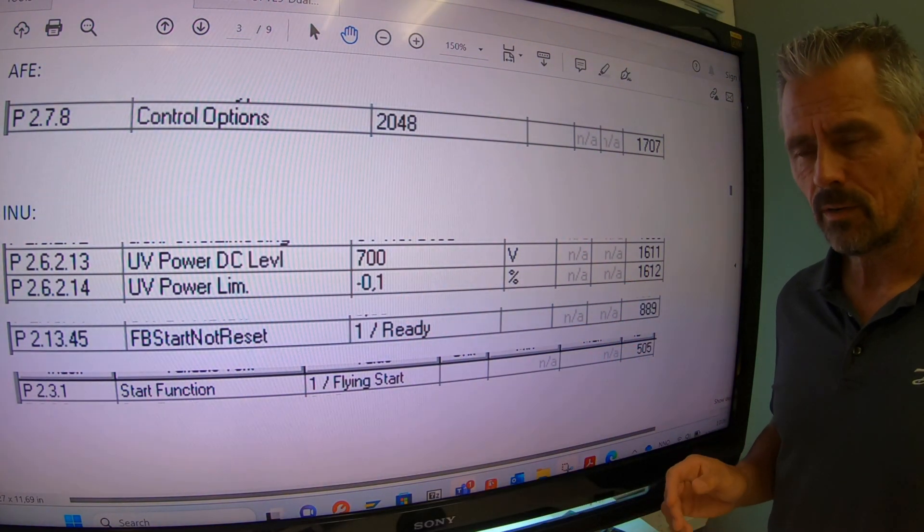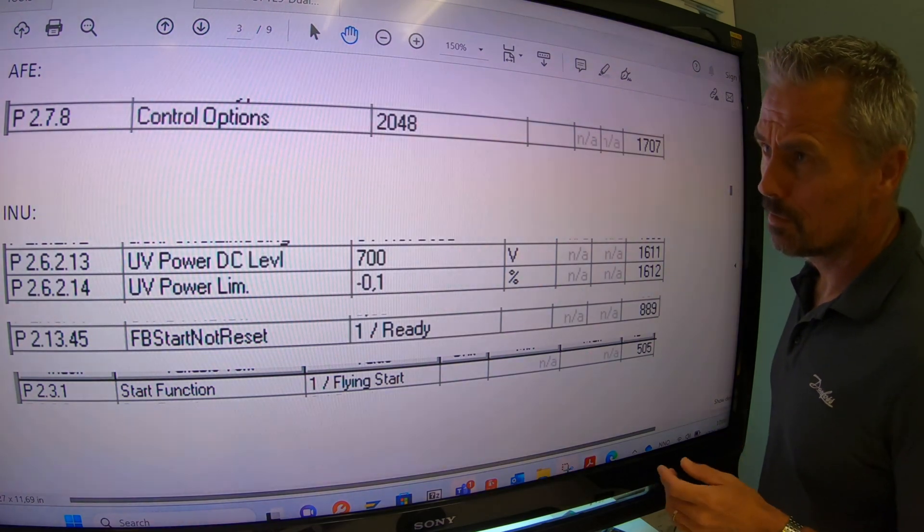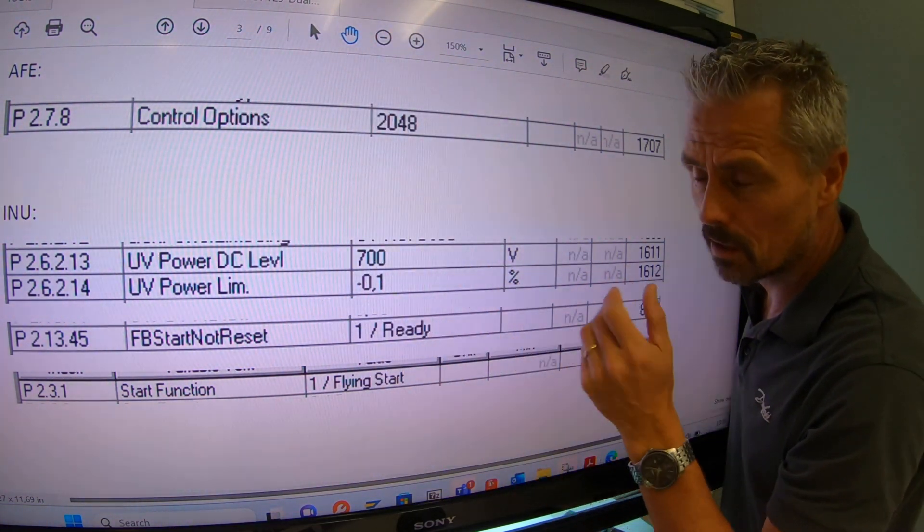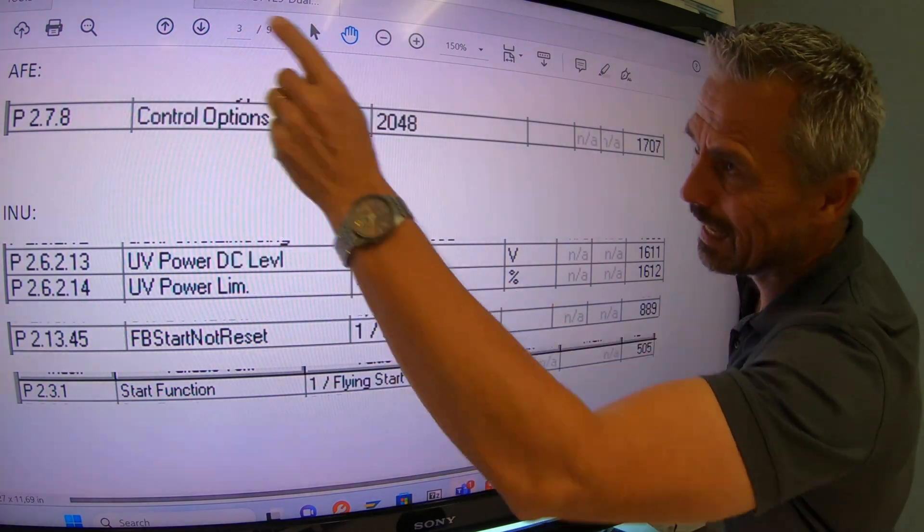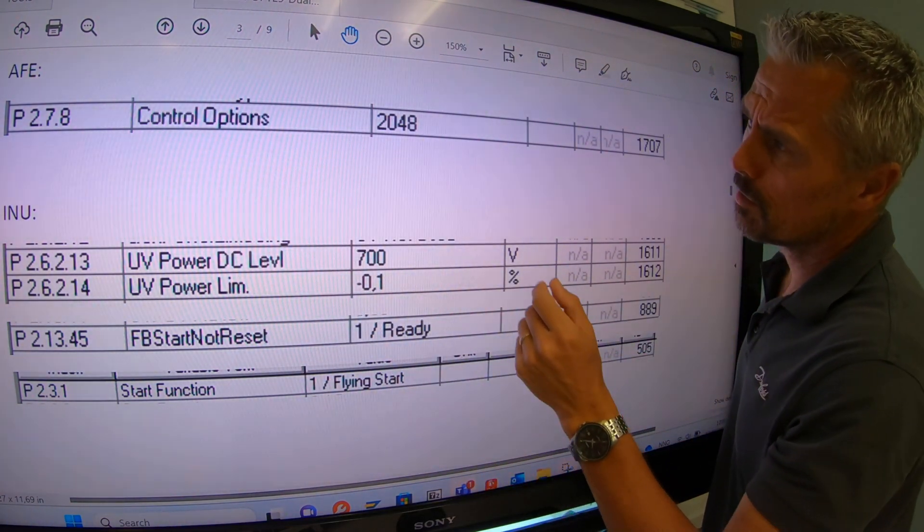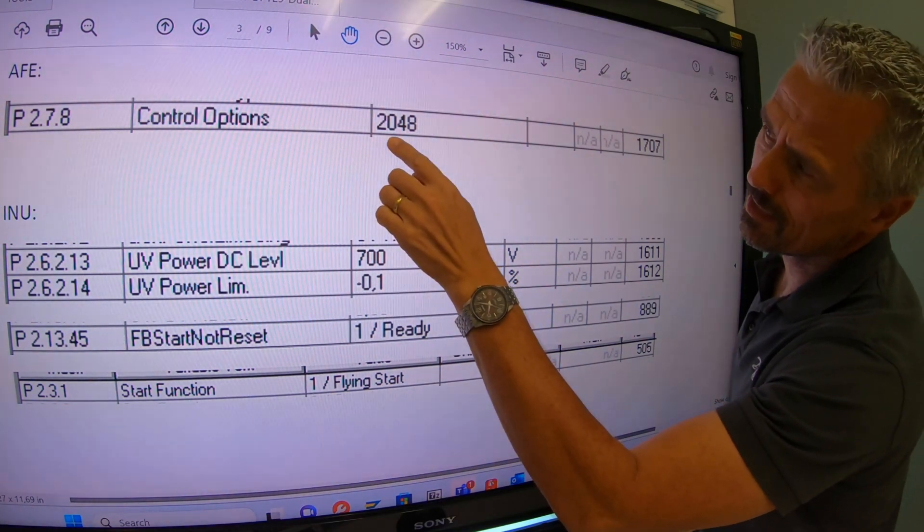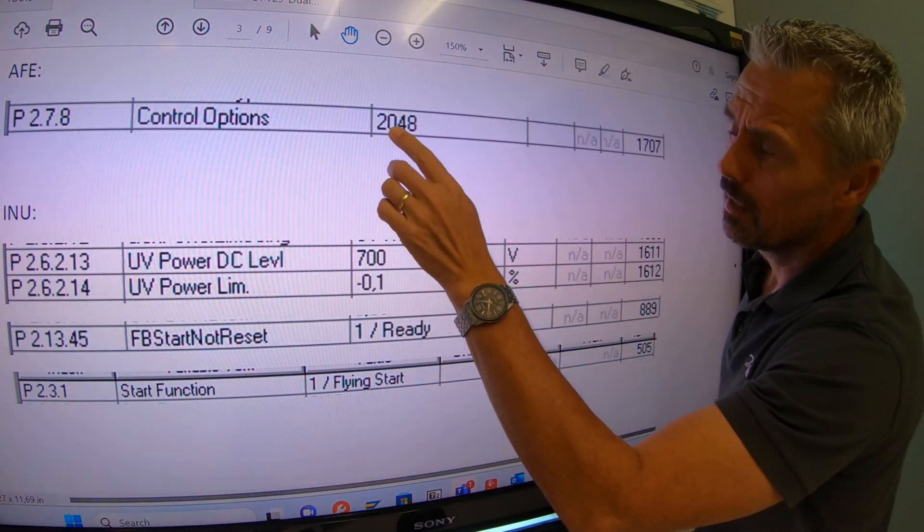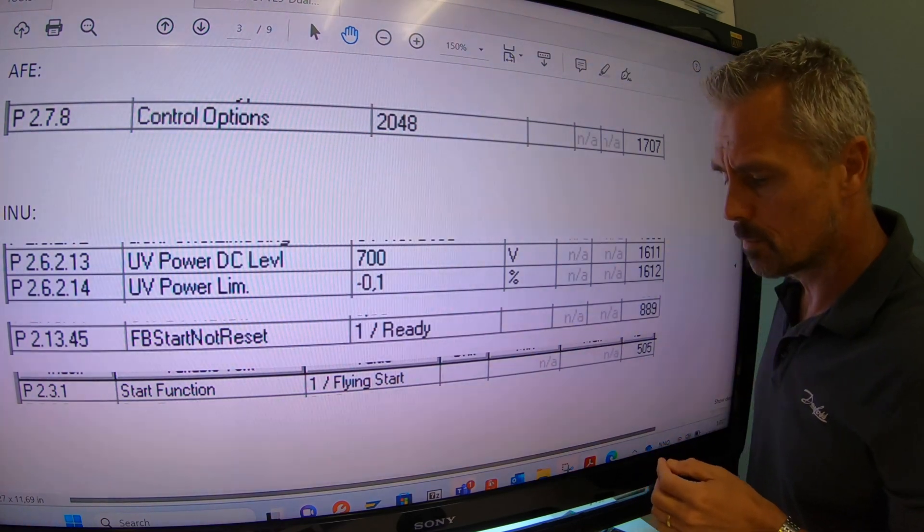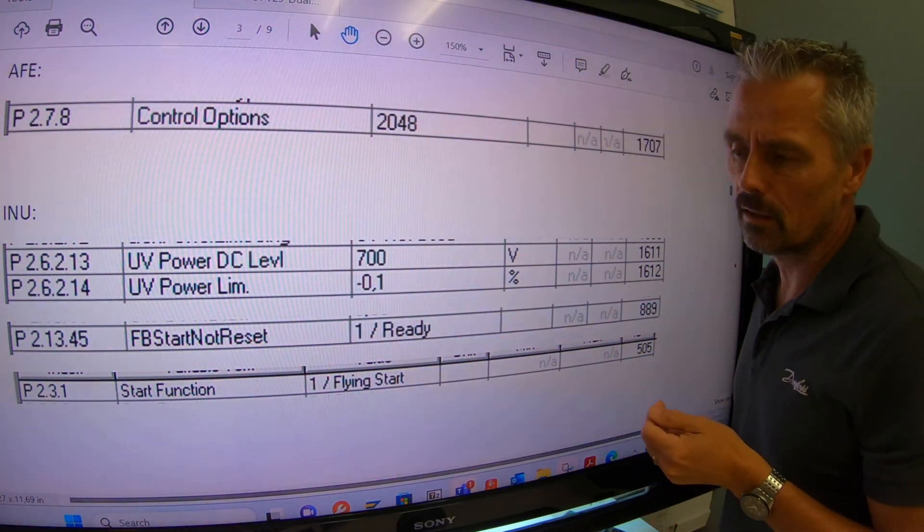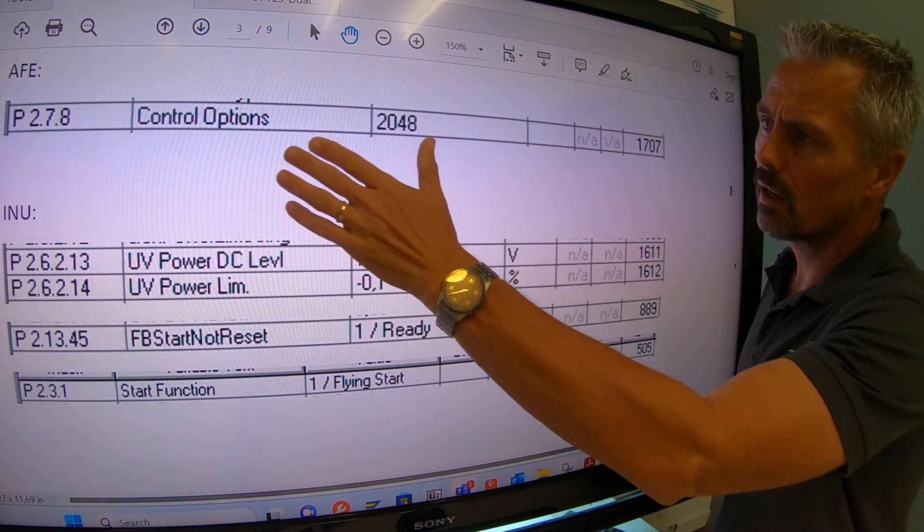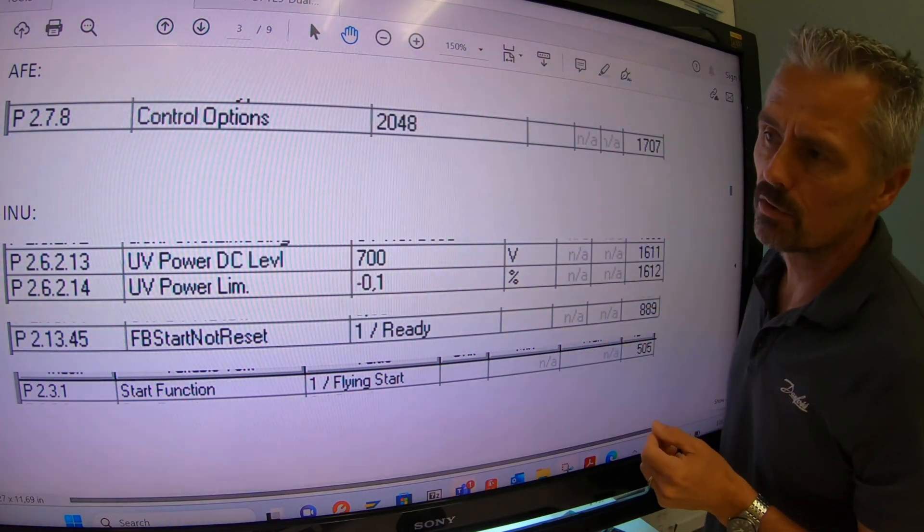Let's start with a quick version showing the parameters needed to get this functionality. In the active frontend, which actually is a grid application in active frontend mode, you need to set bit number 11 in control options. And that is decimal 2048. This will deactivate the supervision of the line sync and the supply voltage. So it will ride through the blackout without tripping these faults.